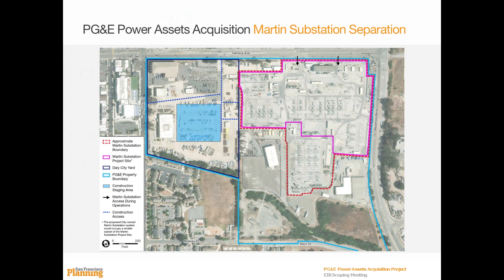Construction would entail a sequence of disconnecting and reconnecting the types of equipment shown on the next slide, installing underground duct banks and vaults, and installing above-ground structures such as control houses, circuit breakers, and transformers. Excavation to access existing duct banks for reconnection, as well as construction of new underground duct banks and vaults to connect the equipment within the Martin Substation Project area, would be necessary to separate the two systems.